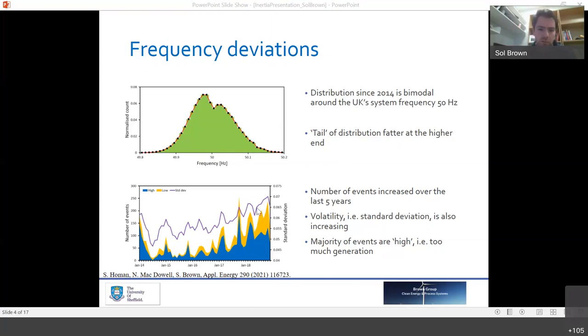What we want to do is to map that over an amount of time, and not only the number of events but the standard deviation. So what is the volatility or the size of each event, and how many major events occur over the past 5 or 6 years? You can see that the number of events is steadily increasing, both high and low events, and we look for a correlation between those and what's happening on the grid itself.